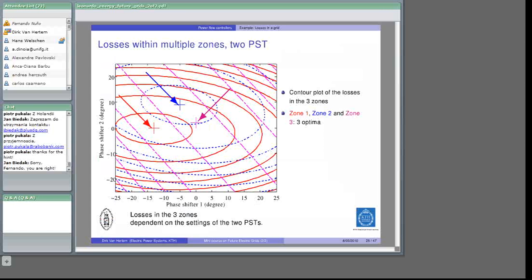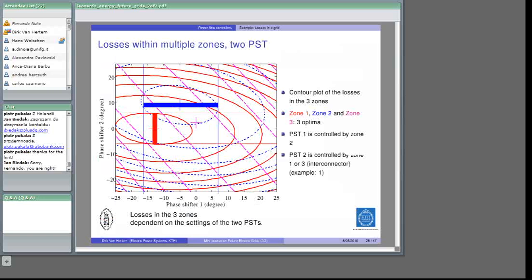Let us say that the first power flow controlling device is operated by zone 2 and it will be operated somewhere at its lowest point. So let's say that in that area is somewhere where zone 2 wants to have its operation. And if we then look at the second PST, which is controlled by zone 1 or zone 3, let's say zone 1 in this case, it will be operated in the indicated area there. And as a result, we can see that the operation area is actually not good for zone 2, which invested in a phase shifter. So it's some kind of suboptimal optimization.